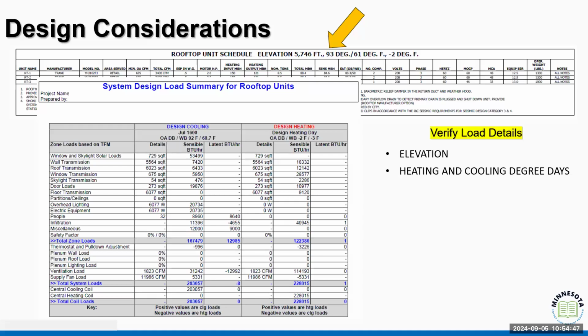If we're looking at a design, we've had this conversation with a variety of building officials and practitioners, some mechanical groups within the state already—we need to make sure the equipment calculation is being run for the appropriate elevation and the appropriate heating climate. If a company works with several different architects in different areas, think about a convenience store or gas station chain that moves into an area—sometimes the design is just a copy of another location, so you've got to make sure that when they calculated the elevation, they got it correct.